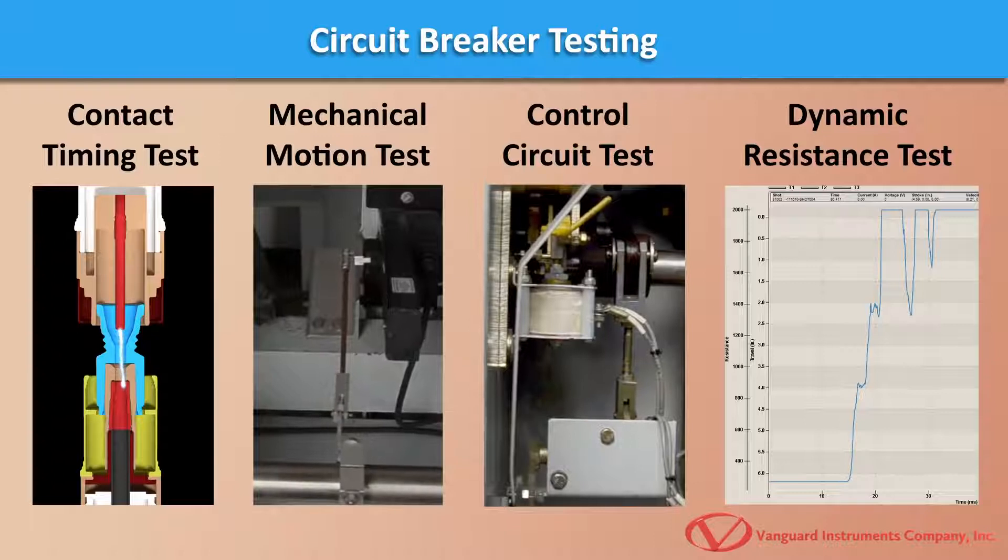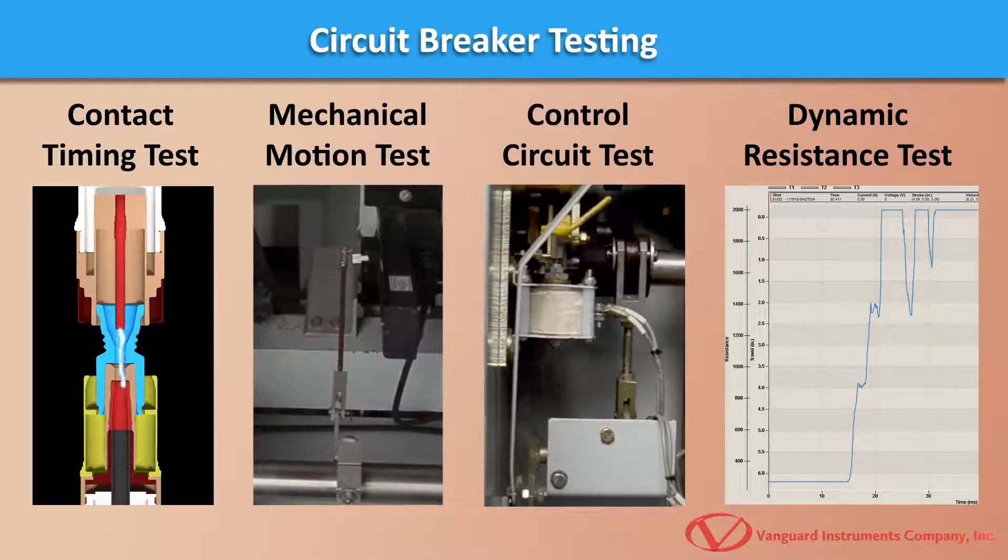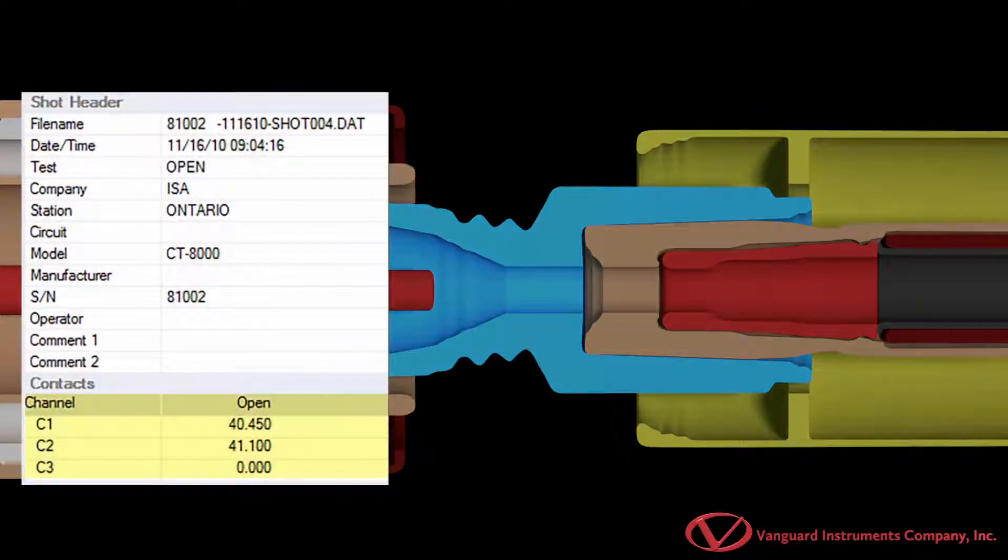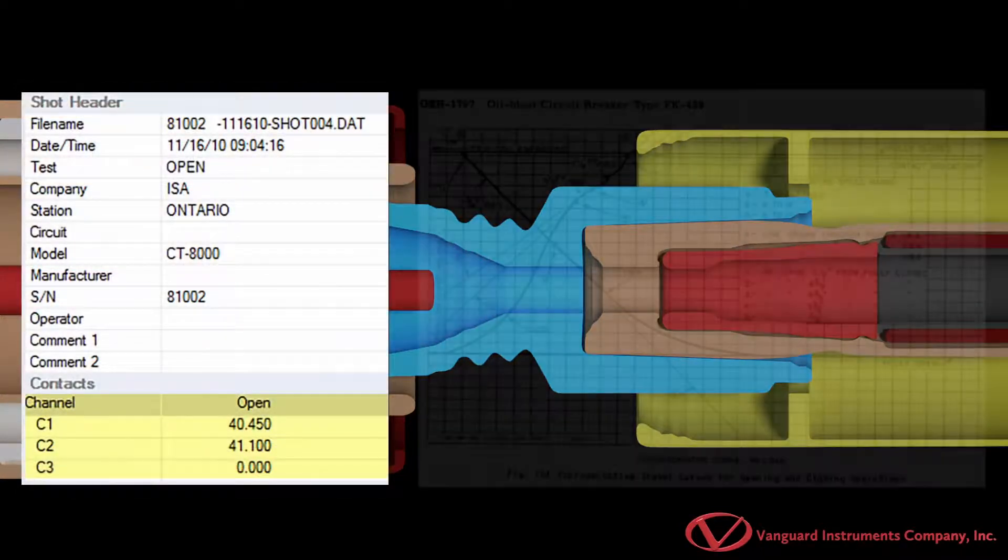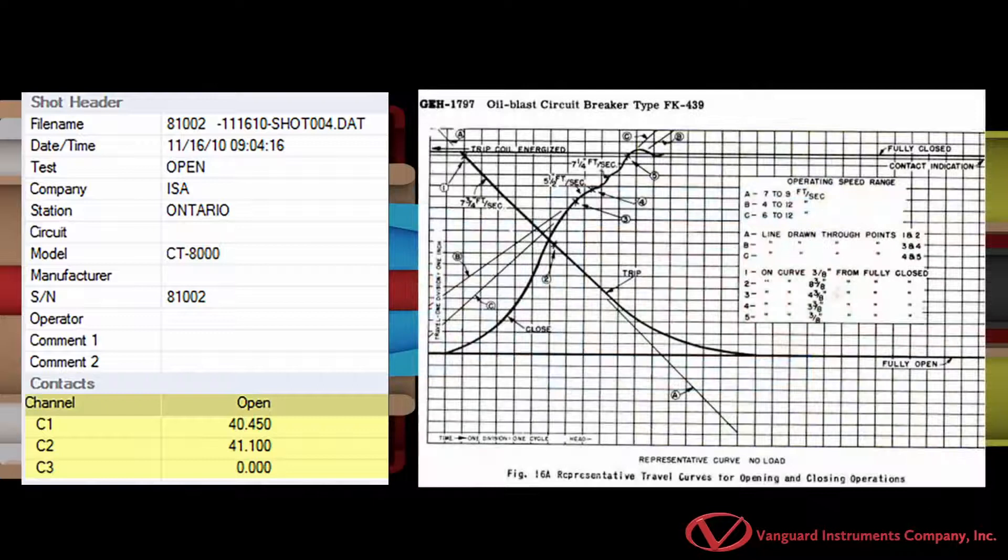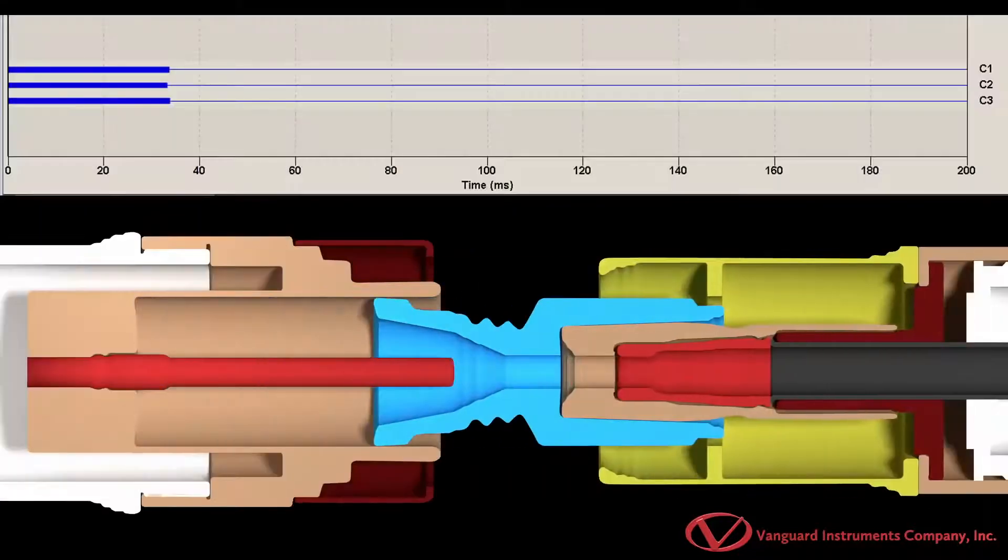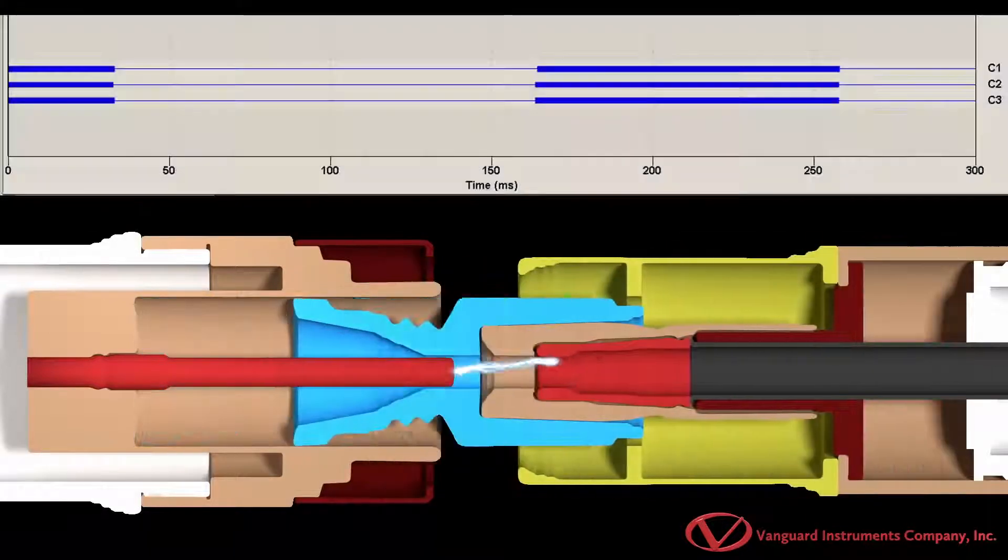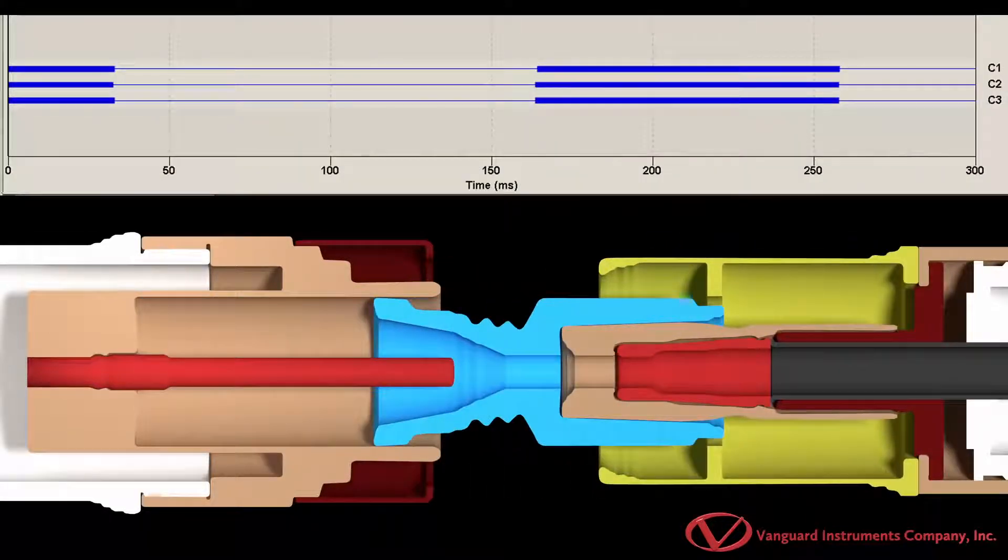Various tests can be performed to evaluate the different components of a circuit breaker. Contact timing tests are used to compare the breaker's main and resistor contact performance against the manufacturer's specifications. The breaker's open, close, open-close, close-open, and open-close-open operations are timed in milliseconds and cycles and compared with the manufacturer's specifications to determine the performance of the breaker.